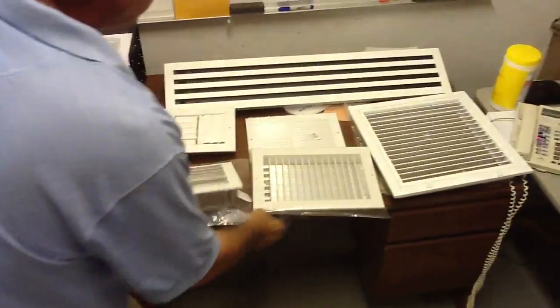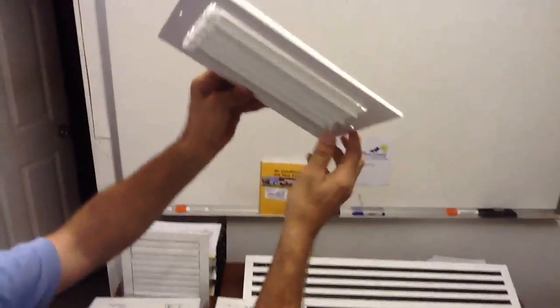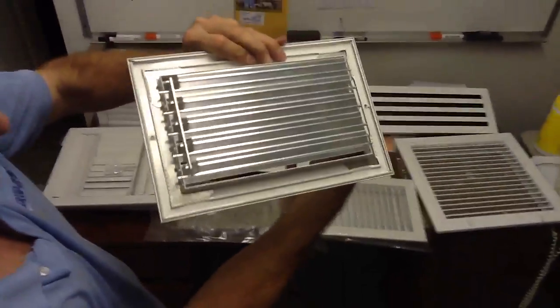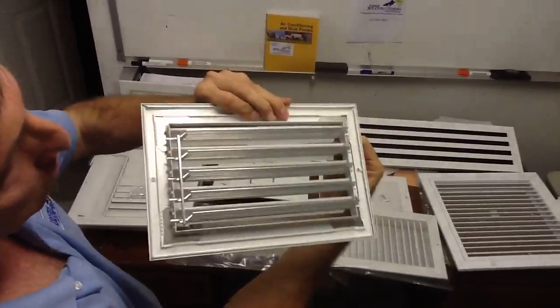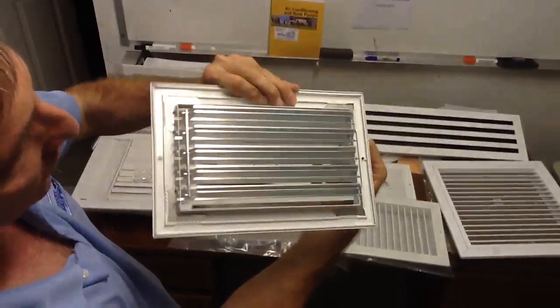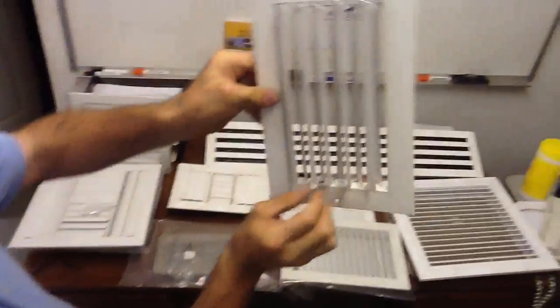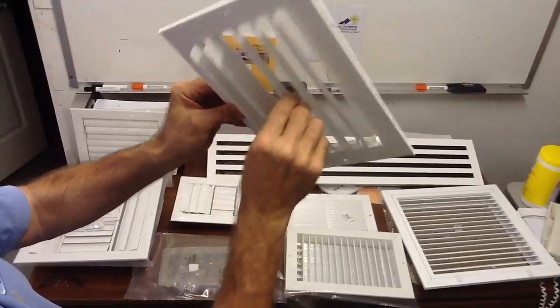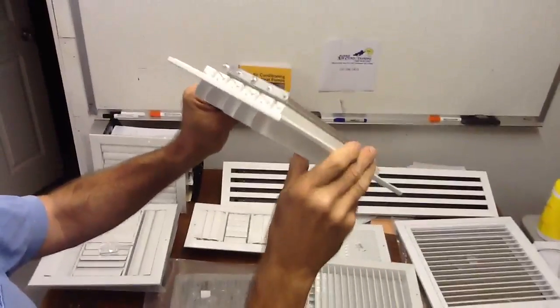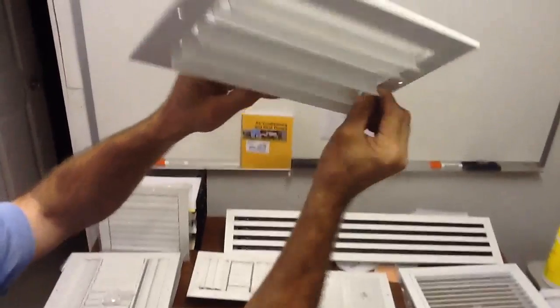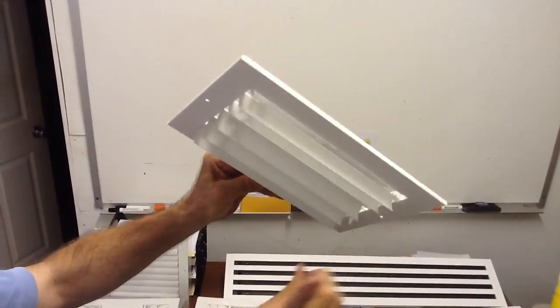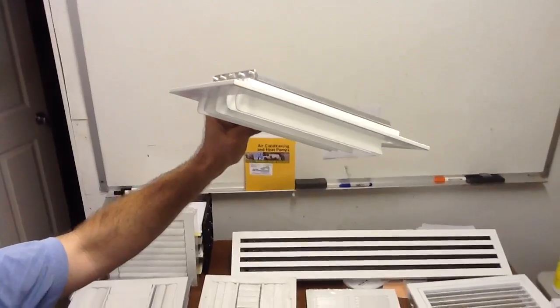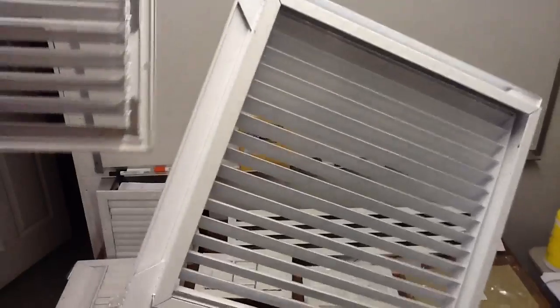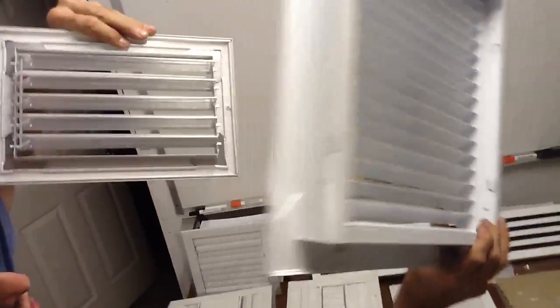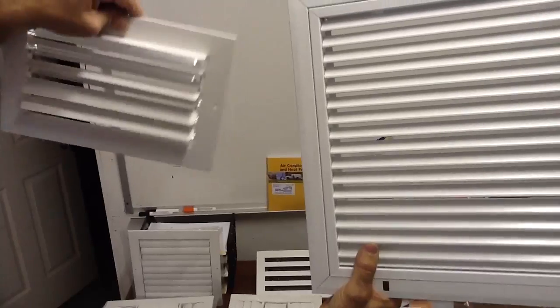One thing I want to point out, this is a supply register, and the difference between a supply register, see how I'm moving this? A supply register has adjustable grills. It's adjustable vents in the back that you can open and close the airflow. You also can move the vents itself, and you can direct the airflow down, more out, more to 45, whatever. At the same time, you can move the airflow, okay? The difference between a supply register and a return grill is a return grill has no louvers in the back. See the difference? This is a return, and this is a supply.